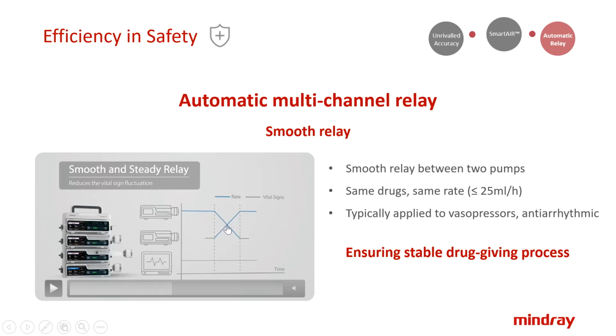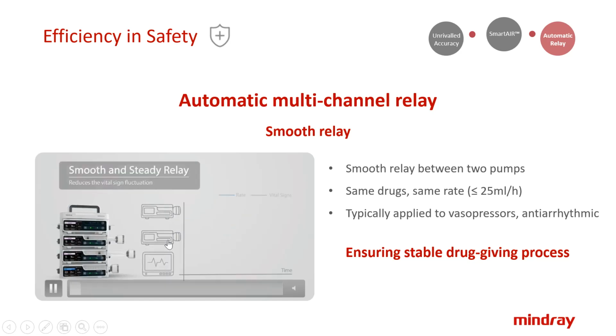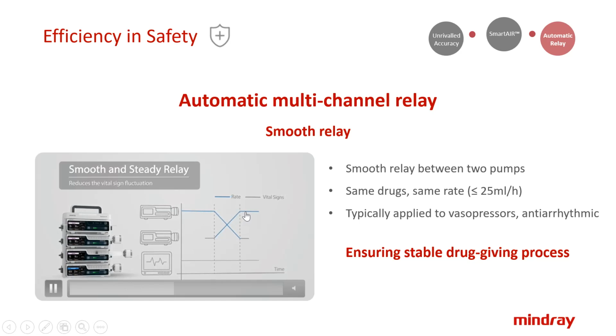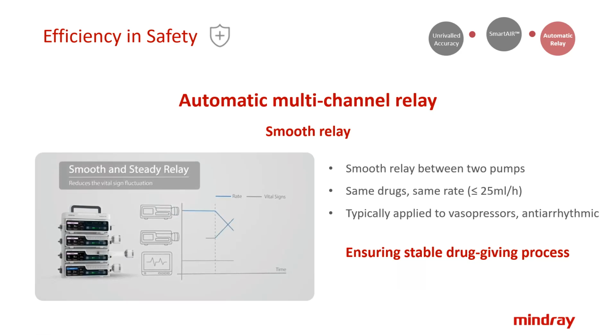And the EDS will just control the first pump to decrease the pump rate and then increase the pump rate on the second pump to make sure the combination of these two pump rates is equal to the preset pump rate. And after the first pump's drugs are used up, the system will just stop the first syringe pump and increase the second syringe pump's pump rate to the preset pump rate. So then, by this function, we ensure a stable drug delivery process and make sure of the safety and the comfort of the animal during the infusions or drug delivery.